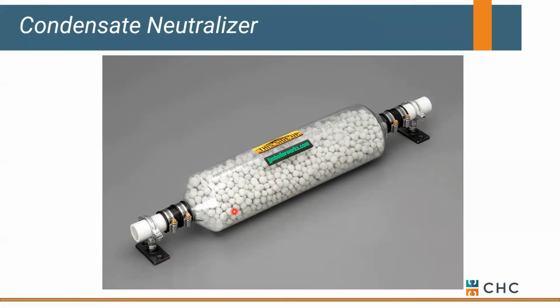If you're mixing it with other fluids, you might be okay, but I'd rather be safe than sorry, and that is to make sure it's neutral before it goes down the drain. If you want to double check your neutralizer, you can put a pH strip over here and take a look at the output, see how acidic it is. Most neutralizers are designed to last a year under full condensing mode, so this is a maintenance item.